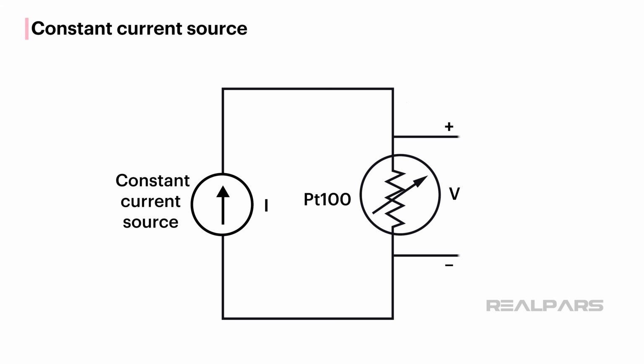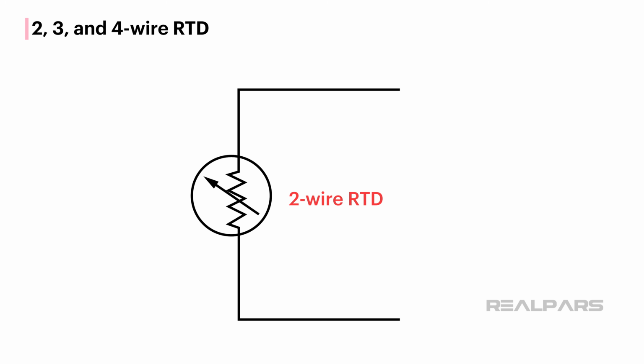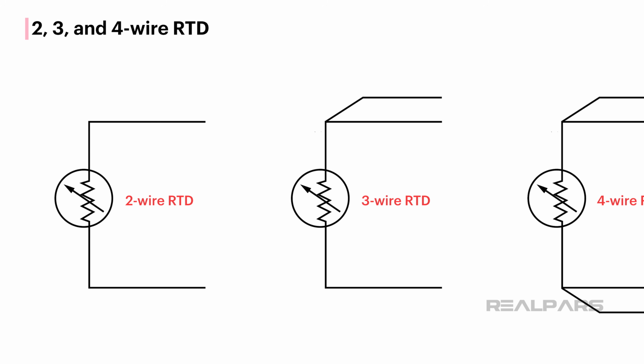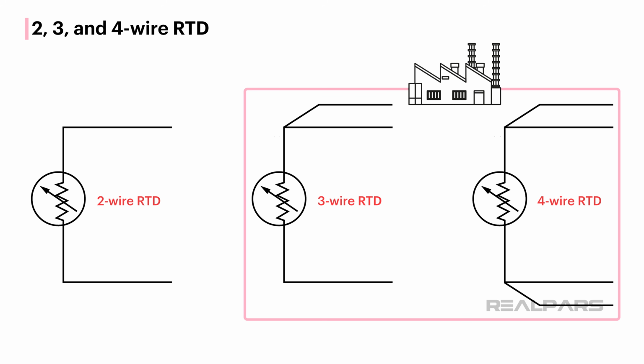So, let's look at better RTD resistance detection methods. The constant current source method is very popular. The voltage V is a direct result of the resistance of the PT100 and the constant current flowing through it. An increase in lead wire resistance does not affect the voltage V because the current through the RTD is not affected. So far, we've only talked about a 2-wire RTD. You will rarely see a 2-wire RTD used in an industrial application because of its inherent problems with resistance detection. 3-wire and 4-wire RTDs are the industry standards, as issues with lead wire resistance are eliminated.